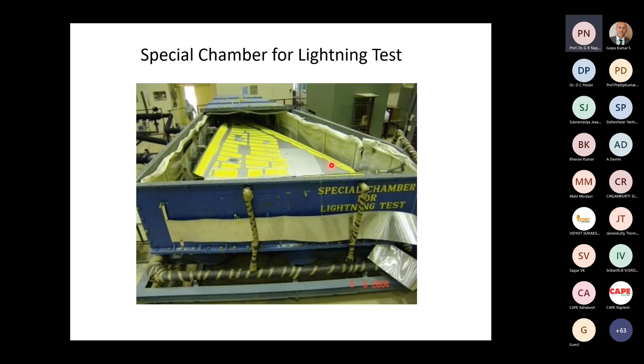So now this wing is filled up with fuel vapor. In fact, we use a vapor of acetylene and something else so that it's far more ignitable than the air-fuel mixture. Therefore, we close it. The chamber top is here. We close it, then fill it up with hot air, fill it up with fuel, and then apply full threat lightning impulses to the selected points, the wing tip and these edges. We apply the pulses. We have supplied it. I'm extremely happy to tell you that the protection scheme worked out has passed dramatically well, with absolutely no failure at all.